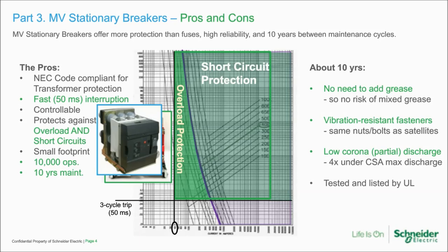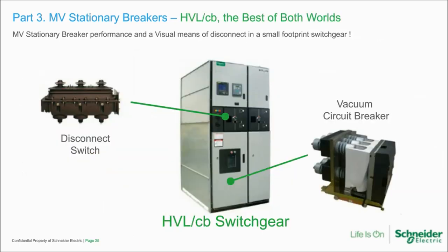HVLCB brings the best of both worlds: breaker technology that gives us the benefits we've already covered, plus a maintenance disconnect switch above it — a no-load switch. All interruption always happens at the breaker, but it allows us to disconnect the entire breaker compartment. And if the option is chosen, ground the entire breaker compartment before opening the door.